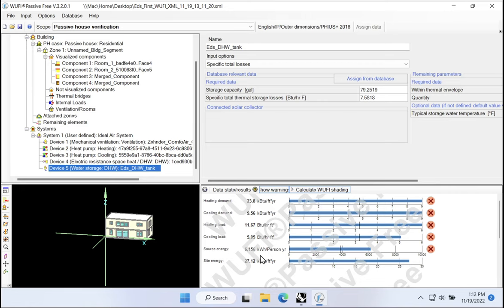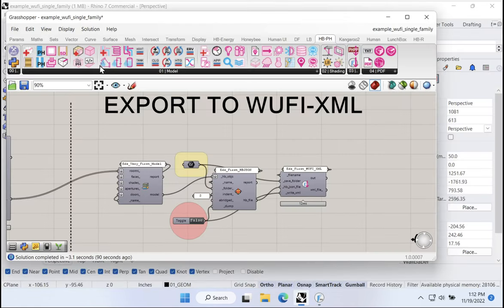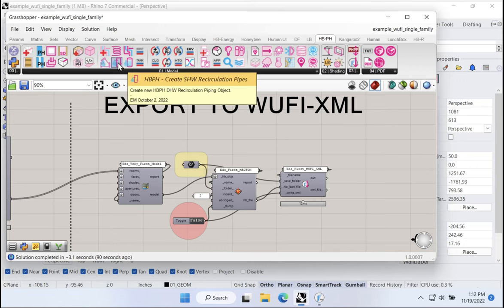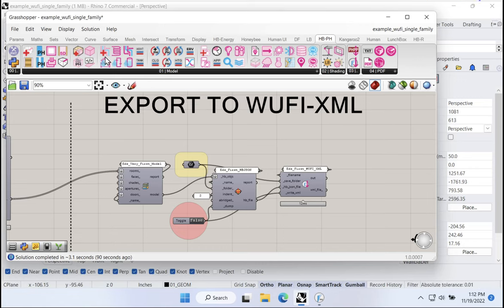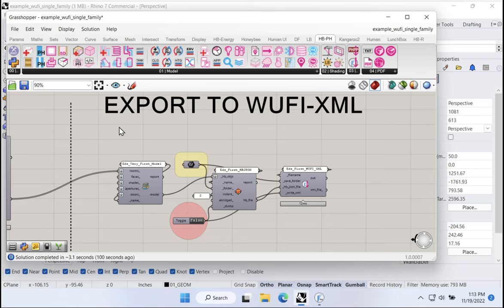There we are. So we have a total source energy of just over 6,000 kilowatt hours per person per year. Now, for a very simple domestic hot water system, that's pretty much all there is to it. There are tools to build out things like domestic hot water piping. Let me go back to Rhino for a second. Of course, there are components up here for things like branch piping, recirculation piping.